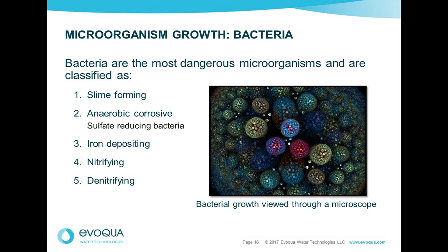And a quick story on nitrifying bacteria. A number of years ago, I was involved with a refinery that had a corrosion problem. Just all of a sudden, in the spring of the year, all their heat exchangers were having leaks like crazy. And they asked me to investigate the system, find out what the problem was. And the first thing I wanted to do is look at the operator log. What's the pH? What happened to the pH? And how much acid are you putting in that cooling tower?